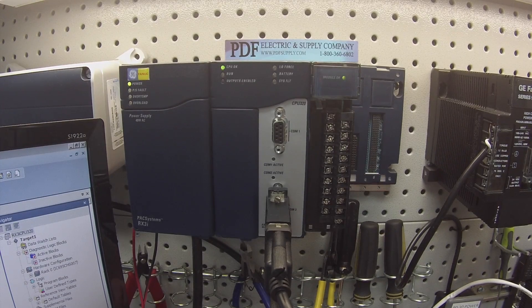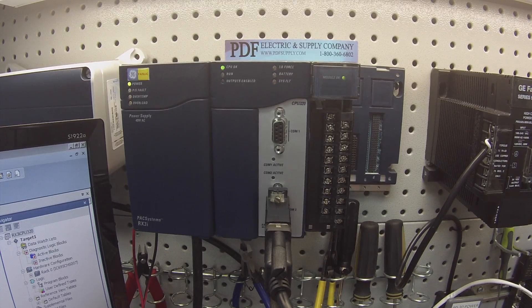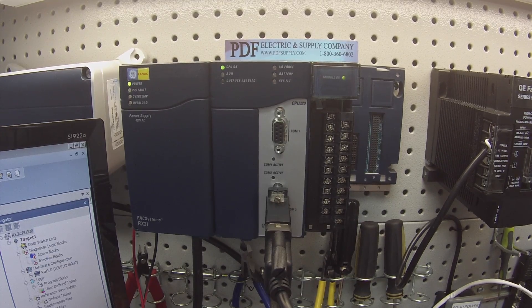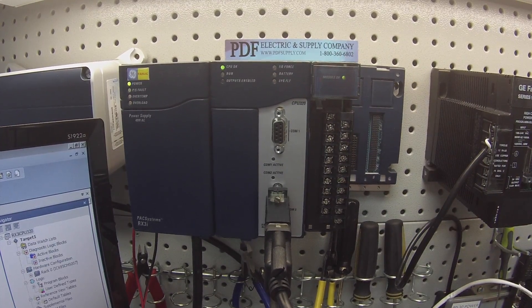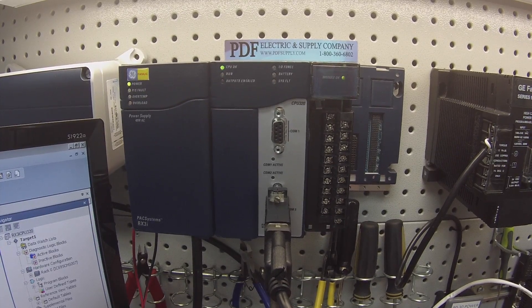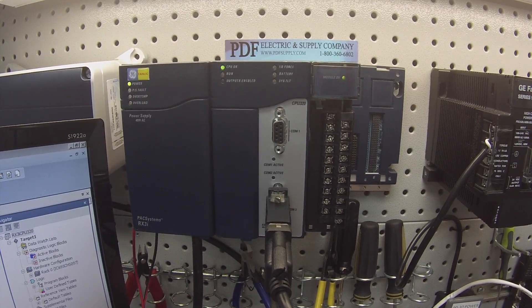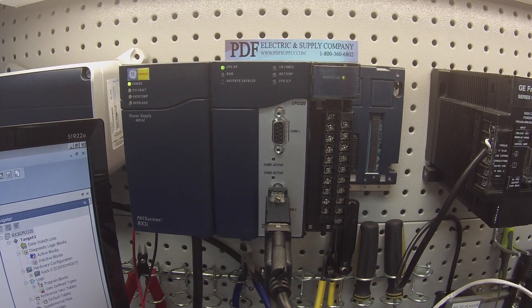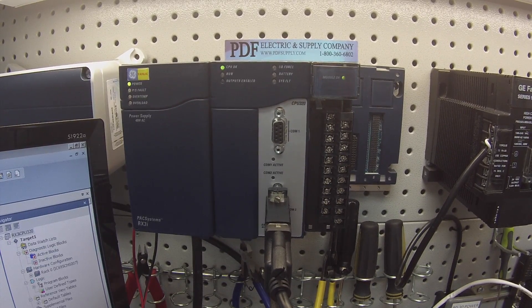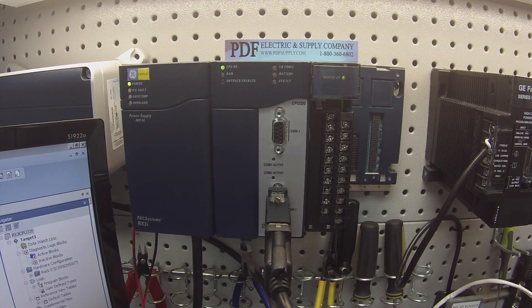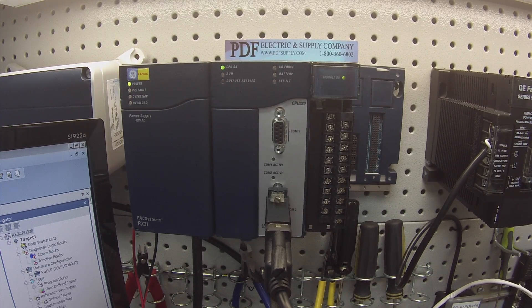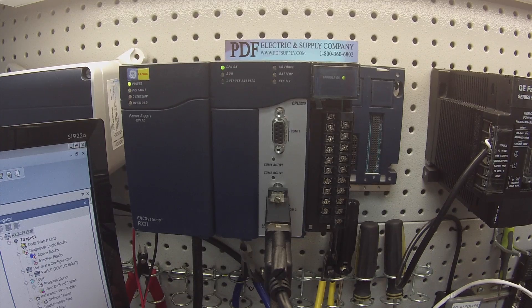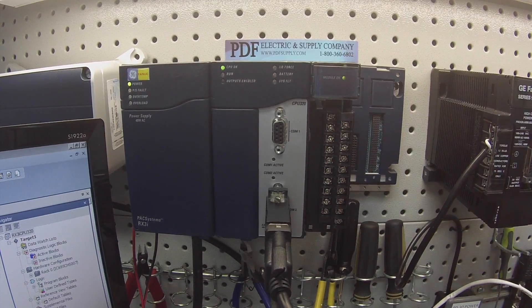Make sure that you have a 24 volt power supply powering up the rack externally to power up this module. Very important. You won't be able to follow this test if you don't get that. Now, if you do have a good 24 volt DC power supply already connected and for some reason you don't get a module OK light on, then that means there's probably something more catastrophically wrong with the module itself, the ALG221. You should get a module OK light if the unit's in good working order.